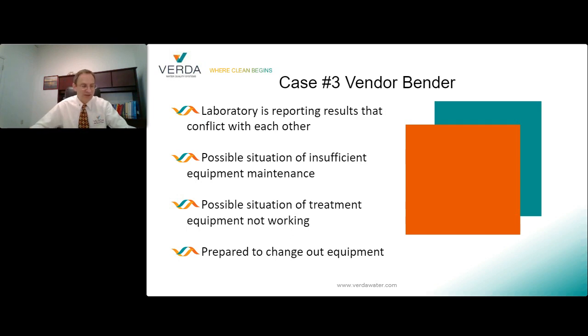I worked with one laboratory that was drawing samples for bacteria testing, and it was common for the samples to indicate over the allowable threshold. Retests were frequent. SPS were having shutdowns for critical water disinfection, and that's common. Shutdowns, the whole story, cancellations, surgery impacts, etc. So I started looking closely at the reports they were creating for my customer. One, they were waiting more than 24 hours to begin the incubation of the samples. Well, the requirement is it should be done the same day, or if you chill it, it has to begin within 24 hours. So they were chilling the samples, but they were keeping them past 24 hours.